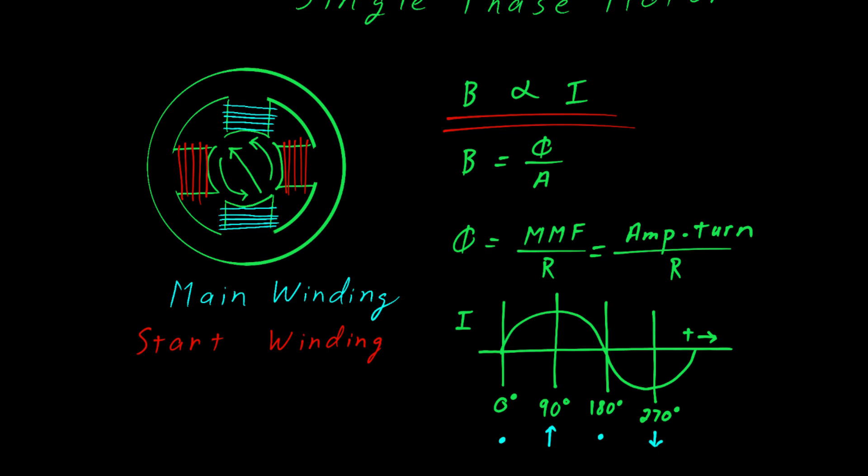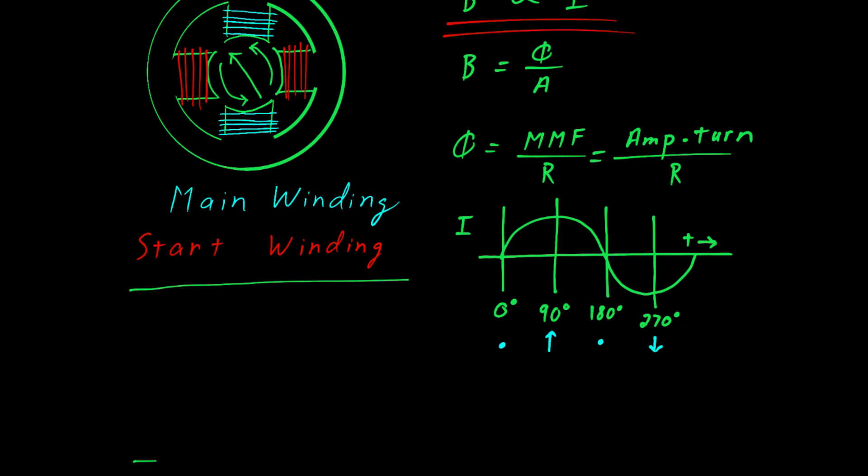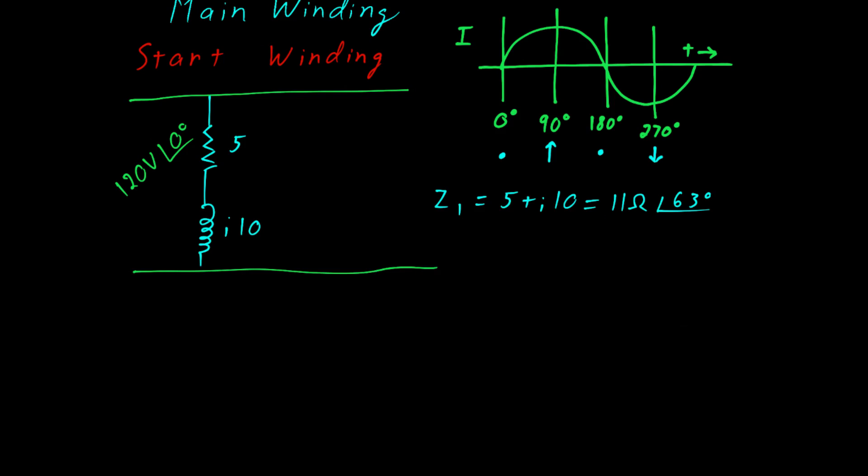Now is a good time to look at the electrical model of the main winding. It consists of two parts, there is a resistance and there's an inductance and we'll pick some arbitrary values of 5 ohms and J10 ohms. We'll also drive it with 120 volts. If you put the two together, let's call it Z1, you'll see that it's 5 plus J10 or if you want to put it in polar form we could say it's 11 ohms at an angle of 63 degrees. At this point we could do a calculation to figure out what the current is but that's not necessary right now. Instead we just want to know the direction of that current and being as it's inductive we know that the current angle is going to be negative, in this case negative 63 degrees.